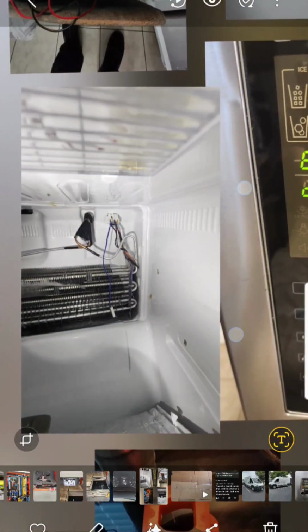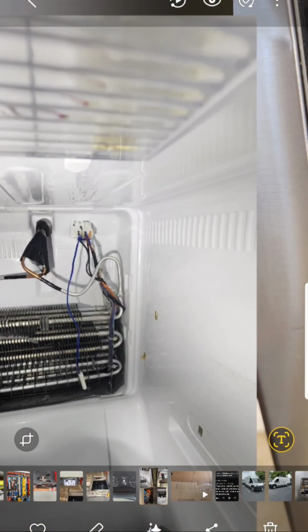But once I tested out the probe, which is right here, and the defrost heater, which is right over here, I tested those out and those checked out fine. Then what I did was I went ahead and used that same probe because it was good. It tested good. So I used that same probe and then I mounted it right up here, right under this insulation right here. And that took care of the issue. That cleared out the error code. And then I mounted that probe where it should be, up on the lines there. And then I put it back into operation.